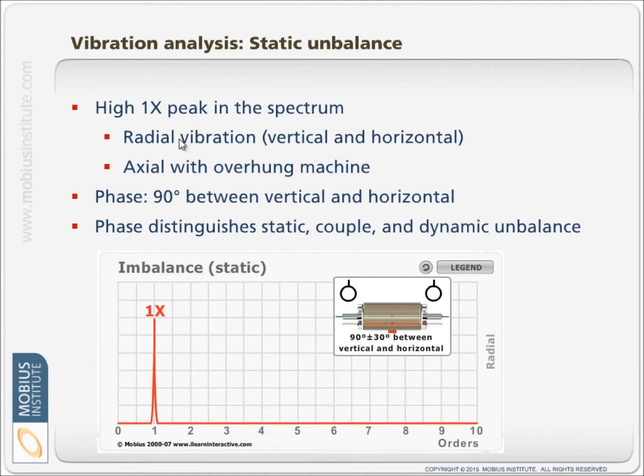So we expect to see the high 1x peak in the spectrum. We see the 90-degree phase relationship between the vertical and horizontal. We would expect to see very little phase difference when comparing the vibration readings at each end of the rotor, and we expect to see the bulk of the vibration in the radial or vertical and horizontal direction and very little axial.